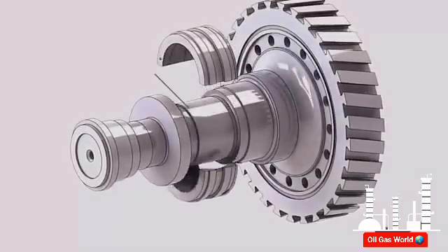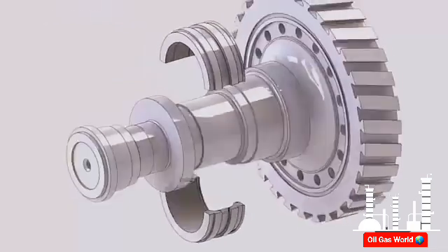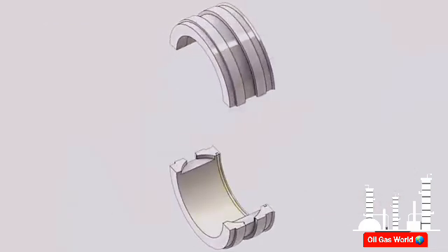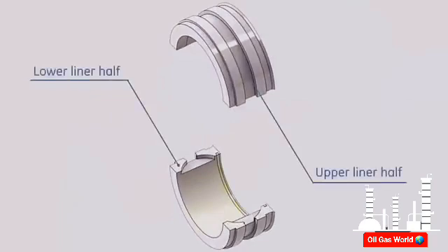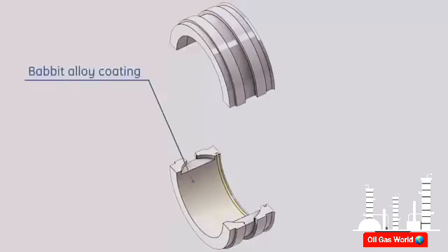The bearing liner and the journal surface are machined on the compressor forward stub shaft. The bearing liner consists of two halves fitted on the bearing housing. The liner inside faces are machined to make convergent oil clearance, in which oil pressure increases around the shaft journal to support it. After machining, these faces are coated with Babbitt alloy.